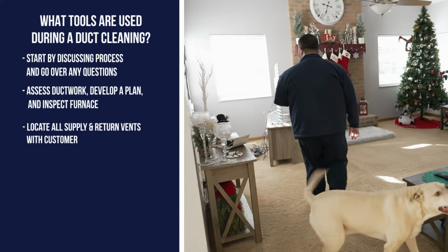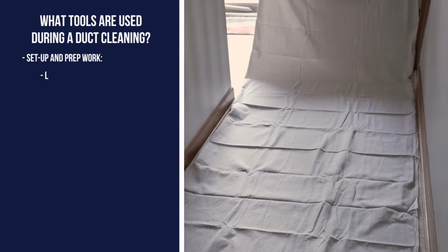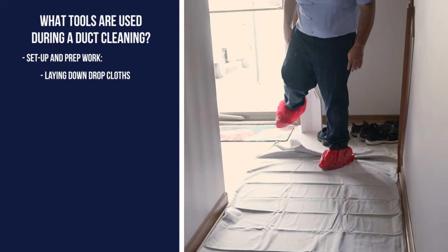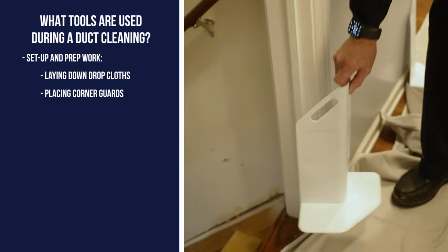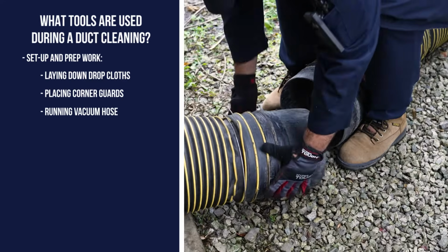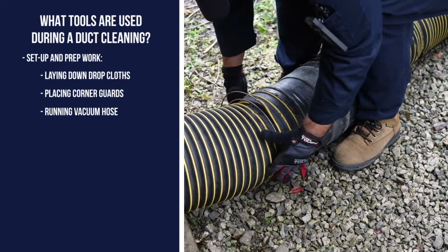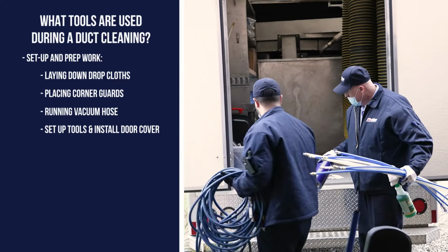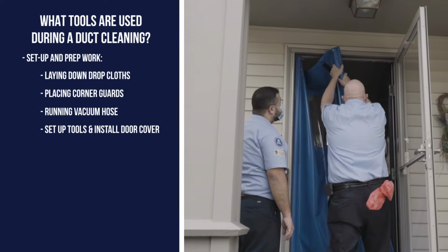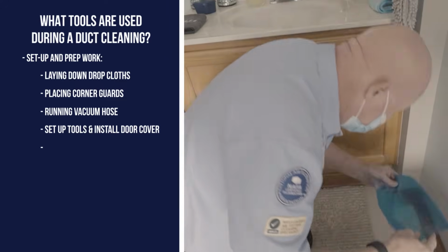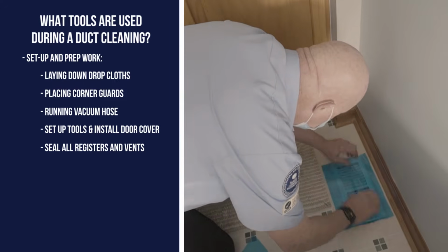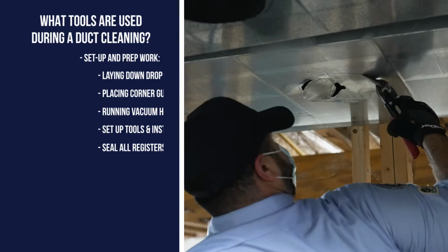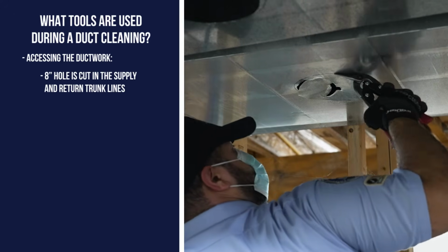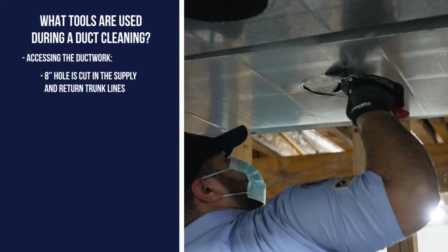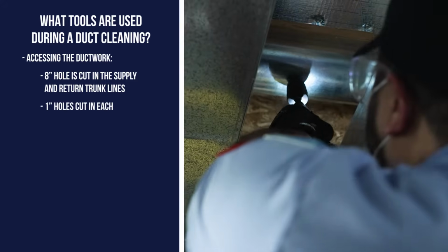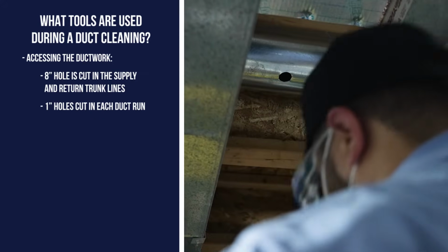Then the prep work begins, which includes laying down drop cloths and protecting the walls with corner guards, running the vacuum hose from the truck to the main trunk line, gathering the compressor hose, setting up all the tools in the workspace, and sealing off all the registers and vents with grill masks. An 8-inch hole is cut in both the supply and return trunk lines for the vacuum to attach to. 1-inch holes are drilled in each duct run as well.